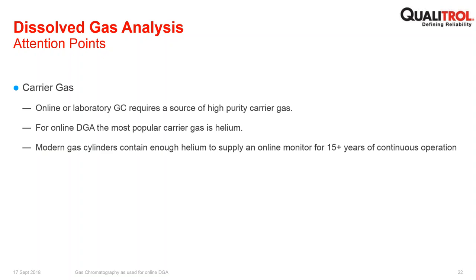Things to note about the use of gas chromatography. The first is, and I've already mentioned it a couple of times, you do need a carrier gas. So this is something which has to be managed. Online or laboratory GC requires this high purity carrier gas. Usually it's 99.9999% purity. It's not difficult to get this. It's available in all countries and from many different gas manufacturers, but it is required.